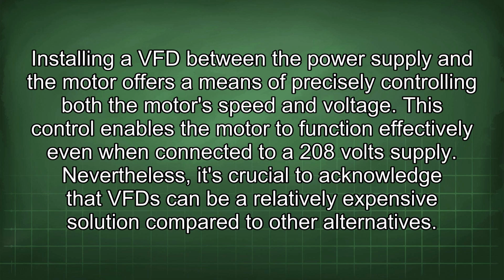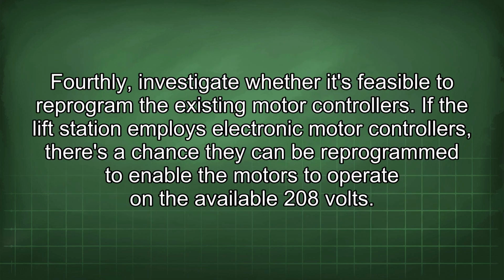Installing a VFD between the power supply and the motor offers a means of precisely controlling both the motor's speed and voltage. This control enables the motor to function effectively even when connected to a 208 volt supply. Nevertheless, it's crucial to acknowledge that a VFD can be a relatively expensive solution compared to other alternatives. Fourthly, investigate whether it's feasible to reprogram the existing motor controllers.